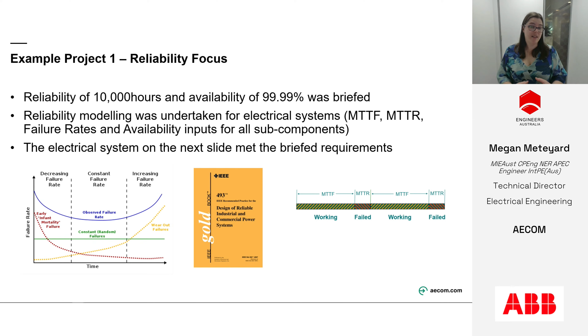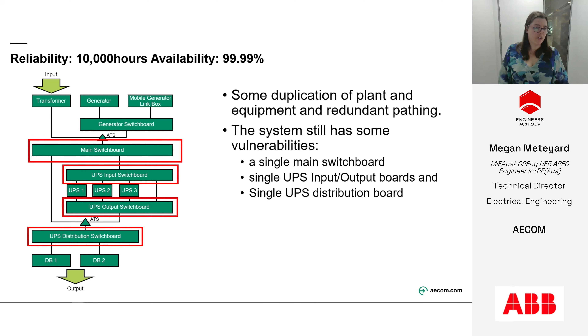The reliability modelling was undertaken. It took into account failure, repair, different failure rates, different availability figures for all the different subcomponents, and that ended up being a system that looks like the system that was shown on the next slide. So you can see that there is some duplication of plant and some redundancy, but there are still some vulnerabilities, like one main switchboard, one UPS input switchboard, one UPS output switchboard, and one UPS distribution system. So despite meeting the client criteria, there are still some vulnerabilities within that system.